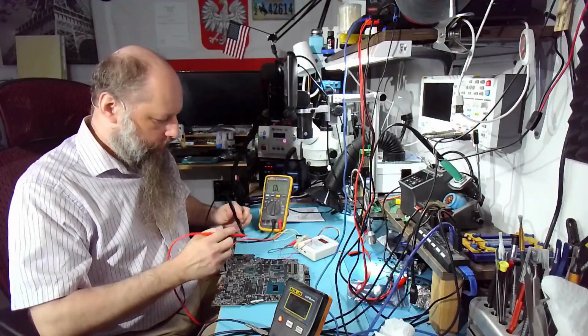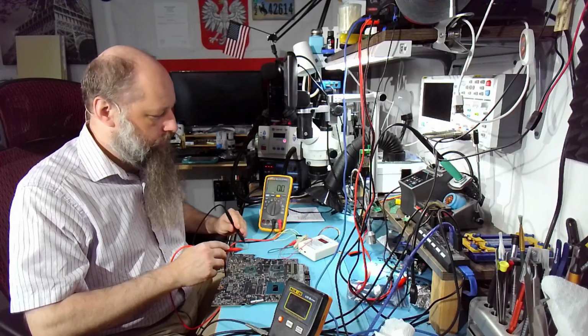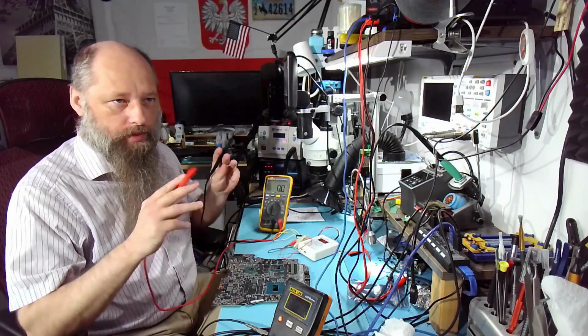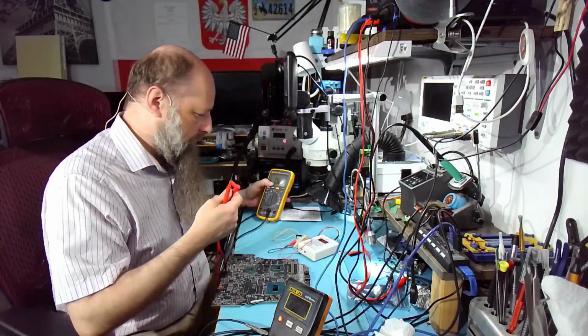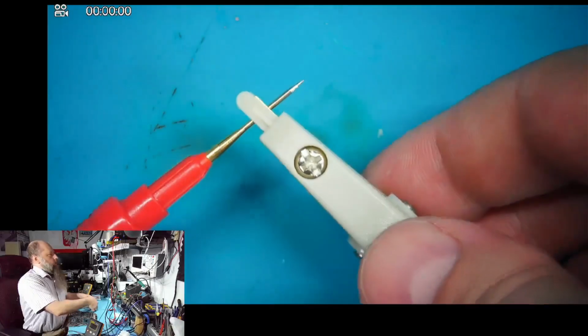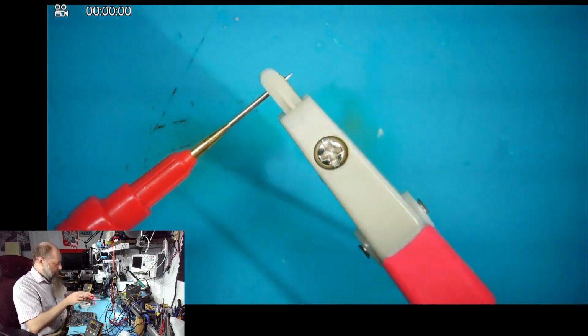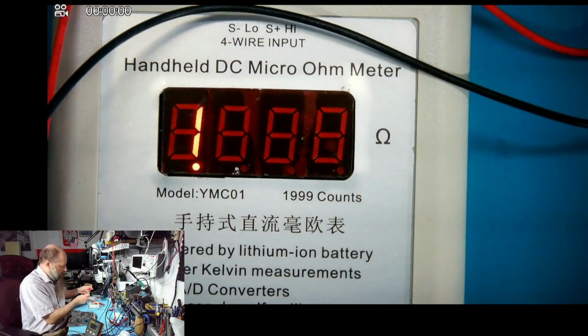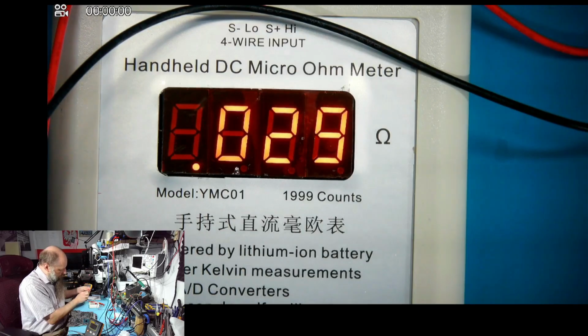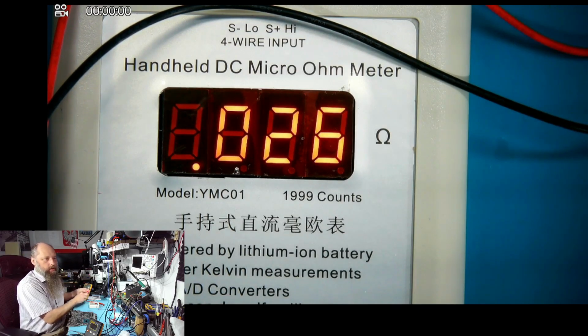self-explanatory. First, let's understand the problem. If we connect these two, we can see that the meter says 0.2, 0.3, 0.1, and 0. Right? That's why it's so unreliable. But it went down to 0. So our probes should have 0 resistance, but do they? What we can do is use the meter to actually measure the series resistance of the probe itself. So we're going to clip one at the end over here. We're going to turn on the meter and we're going to touch this one over here. And the answer is 26. 26 milliohms is the resistance of our probe.